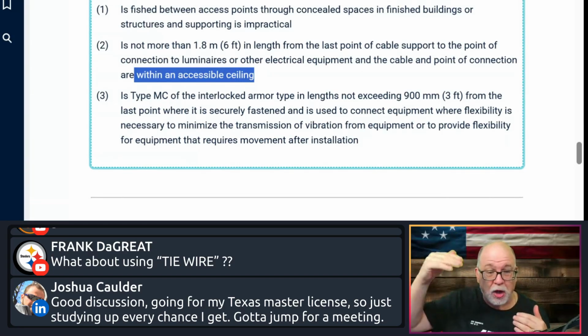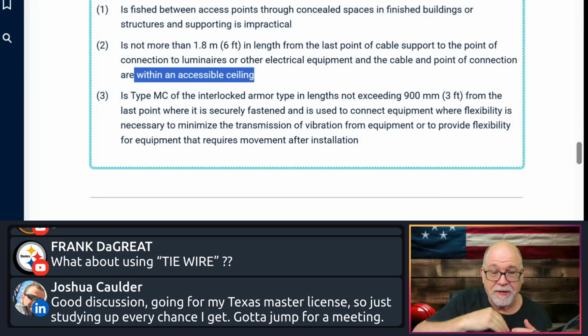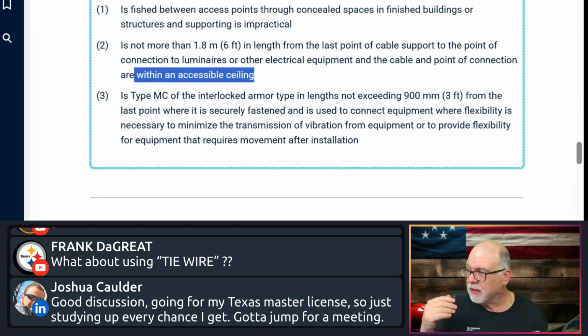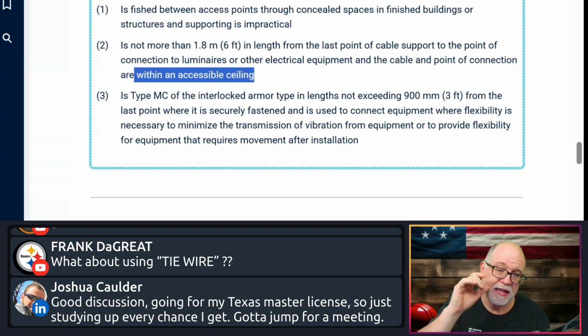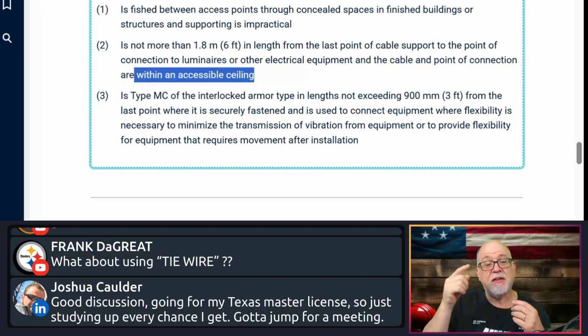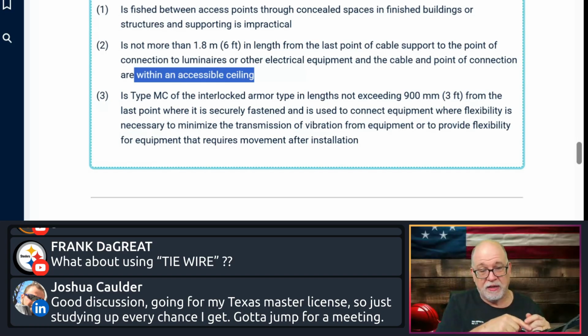That's a whip. We call it a whip. Y'all are familiar with that? Fixture whip, luminaire whip, equipment whip. As long, and this is important because making that statement about the fitting being considered a support, then that means that it can go from that support, which is at the box, up to 6 feet to the luminaire. Words matter. And so this was added in the 2023.